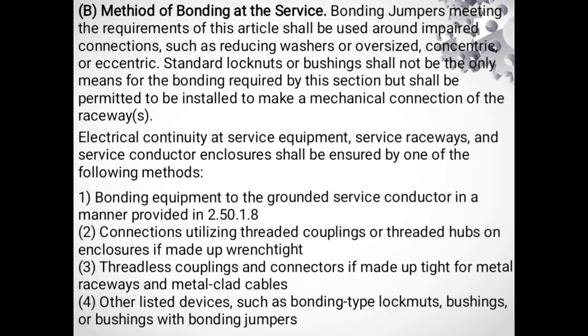B. Method of Bonding at the Service. Bonding Jumpers meeting the requirements of this article shall be used around impaired connections such as reducing washers or oversized, concentric or eccentric knockouts. Standard lock nuts or bushings shall not be the only means for bonding required by this section but shall be permitted to be installed to make a mechanical connection of a raceway.